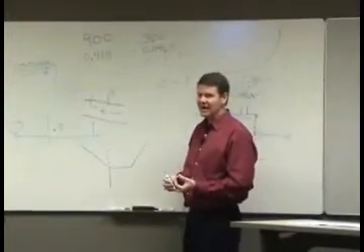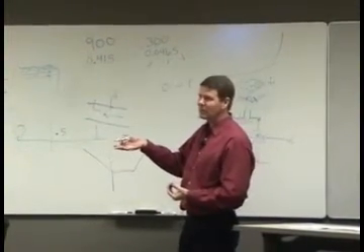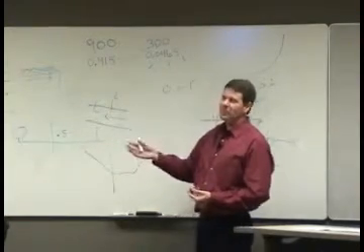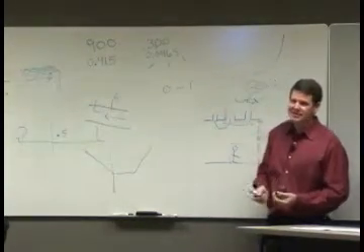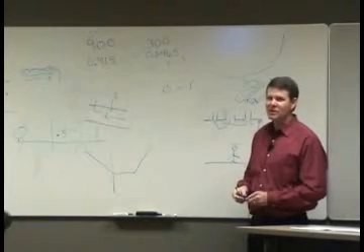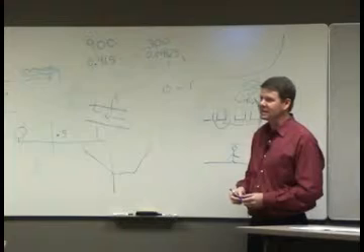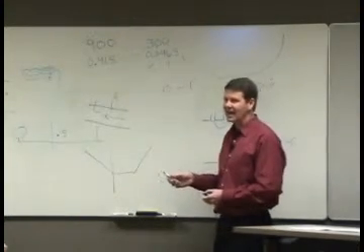Well, if all you've got is minimum CFM, you've got 0.0 something, that might be right. Try and get the box wide open so you get up to where you're reading something above 0.1. In my experience, it'll read below 0.1, but you get much below there and it kind of trails off pretty fast.